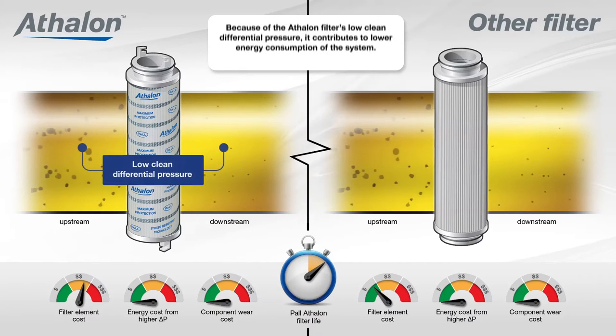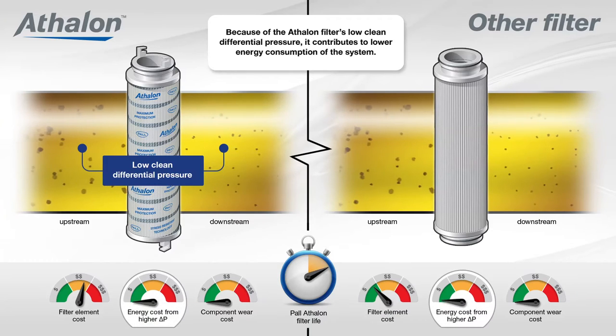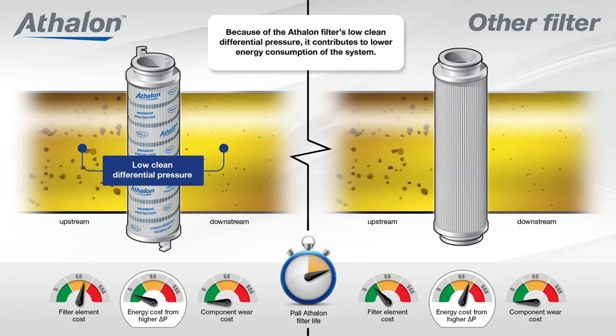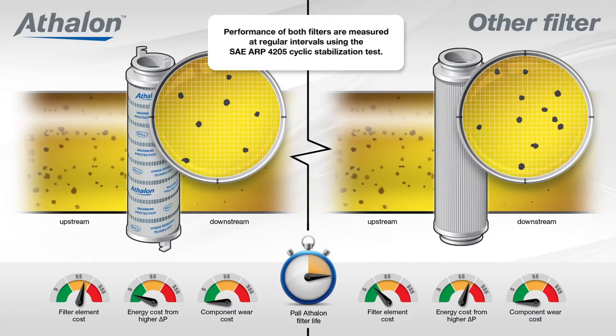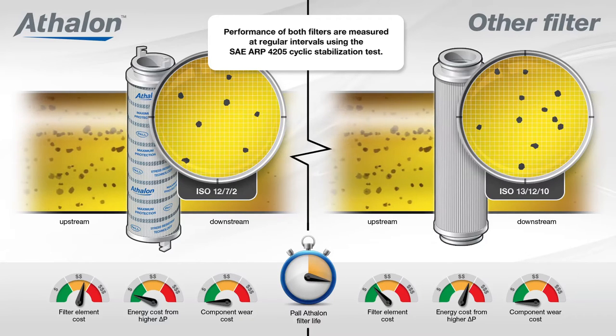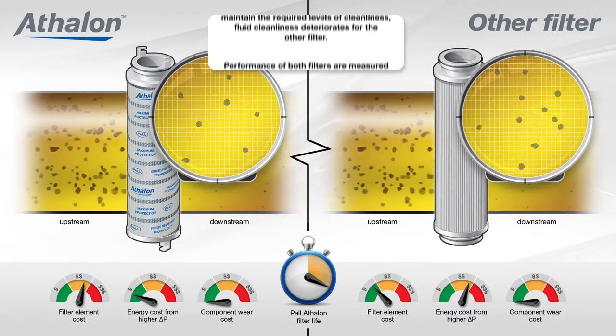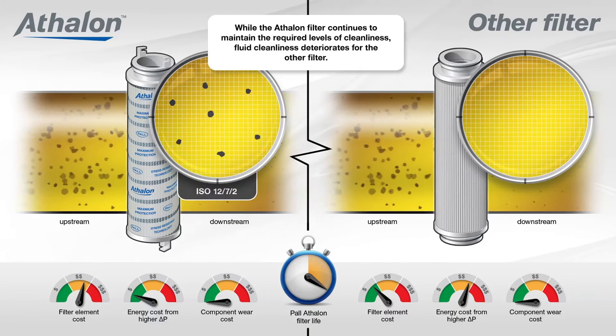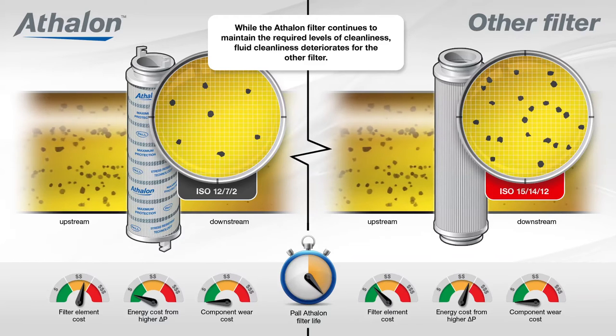Additionally, because of the Athalon filter's low clean differential pressure, it contributes to lower energy consumption of the system. During the test period, the performance of both filters is measured at regular intervals using the SAE ARP 4205 cyclic stabilization test. While the Athalon filter continues to maintain the required levels of cleanliness, fluid cleanliness deteriorates for the other filter.